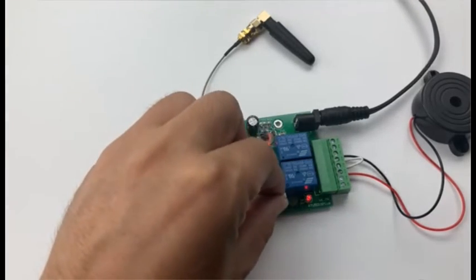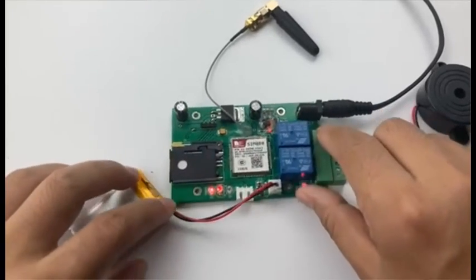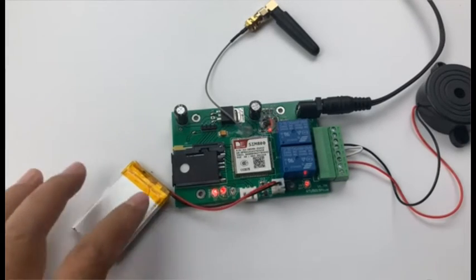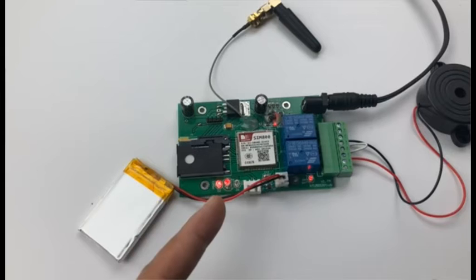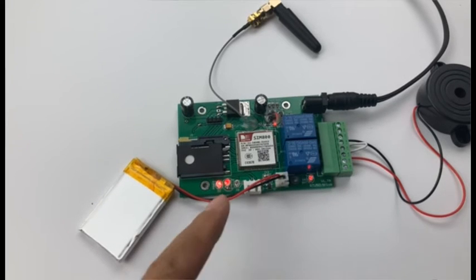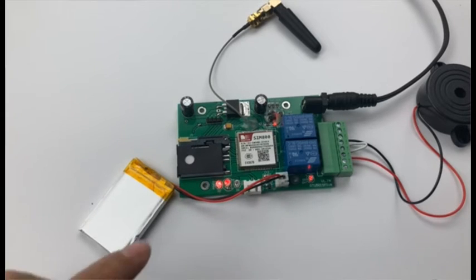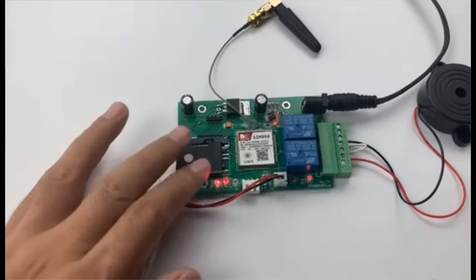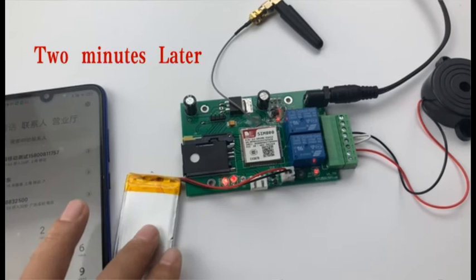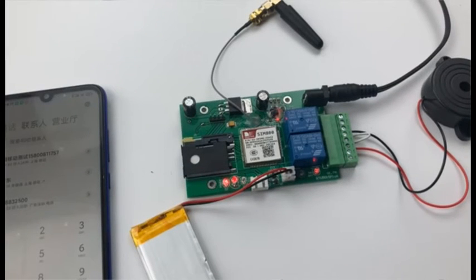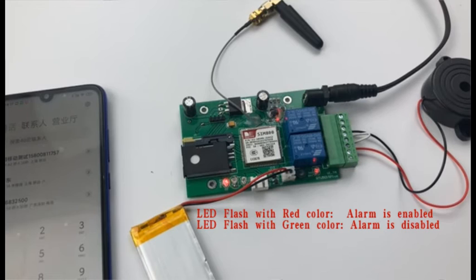Of course, we also plug in the battery. And this LED, after 2 minutes, will flash red. That means alarm is enabled. If it flashes green, that means the alarm is disabled. And we need to wait around 2 minutes. We wait for the first 2 minutes to finish. Okay, the LED has started to flash, and it flashes red. So that means the alarm input is enabled.